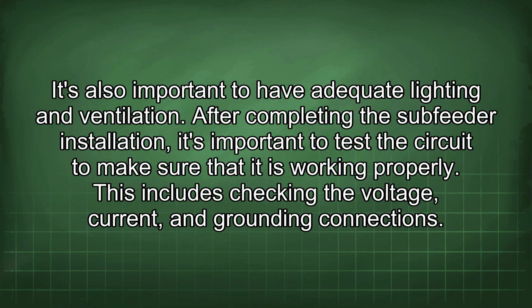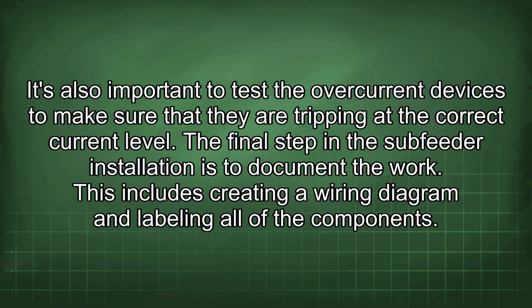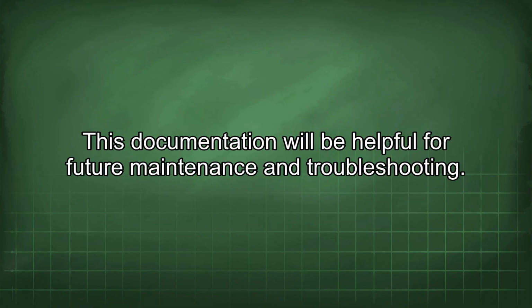After completing the subfeeder installation, it's important to test the circuit to make sure that it is working properly. This includes checking the voltage, current, and grounding connections. It's also important to test the overcurrent devices to make sure that they are tripping at the correct current level. The final step in the subfeeder installation is to document the work. This includes creating a wiring diagram and labeling all of the components. This documentation will be helpful for future maintenance and troubleshooting.